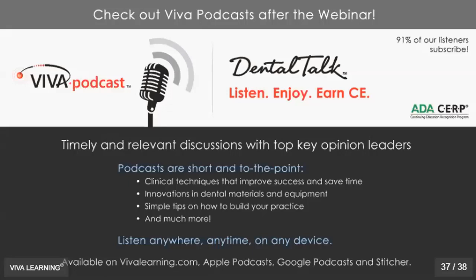There's a question about brand name, about are there pouches that are multi-parameter? And since we're not in the education portion, I can't address a brand name. I can tell you that there are, the SureCheck pouch is a validated multi-parameter, and that particular pouch requires time, temperature, and pressure in the form of steam in order for it to turn. So it exceeds what the ISO standards are for a type 2. There are other ones, and if you read your catalogs, if you ask your sales rep for the documentation on that product, you'll be able to see.